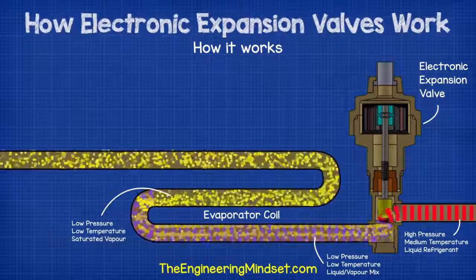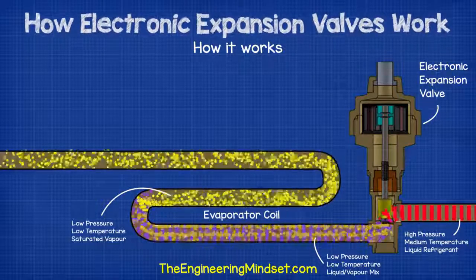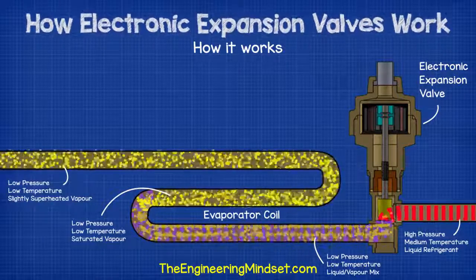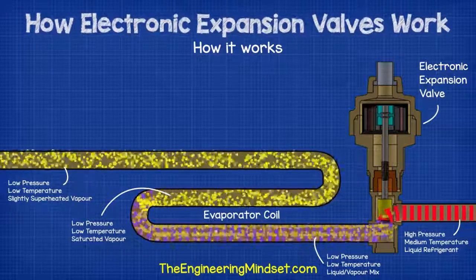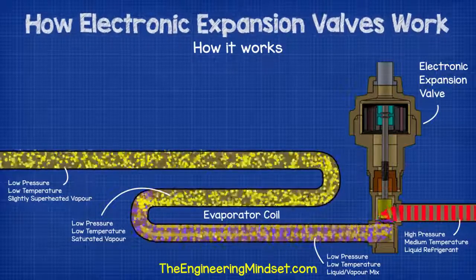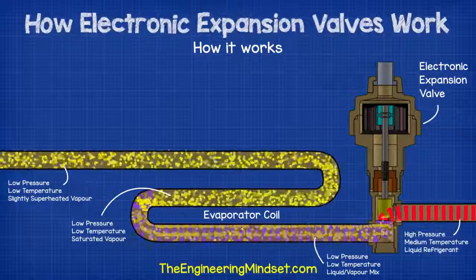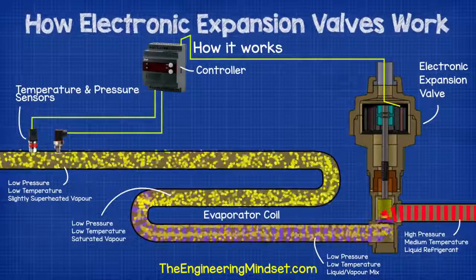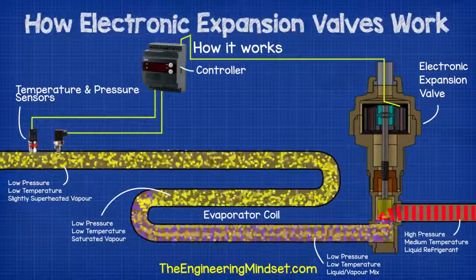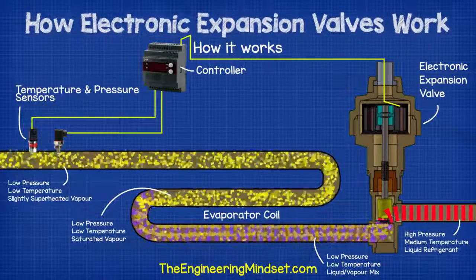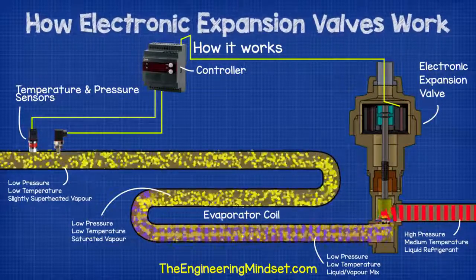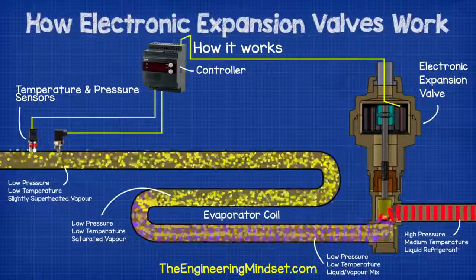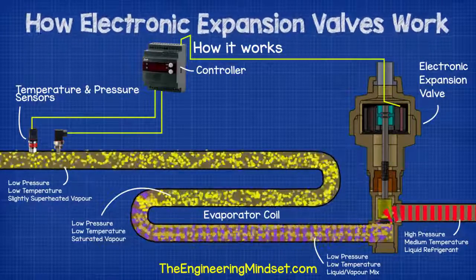As thermal energy is still being applied to the vapor towards the exit of the evaporator, there is no liquid left over to change into a gas form, so the refrigerant will instead start to increase in temperature and become superheated. After the evaporator, we'll find a pressure transducer and a temperature sensor which constantly take measurements and send this data to the controller. Not all electronic expansion valves will use this method. It really depends on the manufacturer and the system.